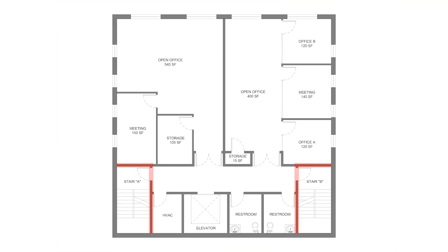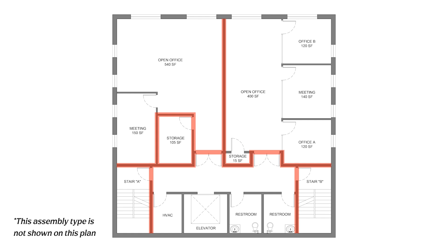Note that stories or numbers of floors in a building include basements but exclude mezzanines. Other walls that must have a one hour fire rating are tenant dividing walls, walls that separate a tenant from a public corridor, storage rooms exceeding 100 square feet, and certain assembly occupancies of 750 square feet or greater with an occupant load of 50 people or more. Some other variables that may determine fire rating are the building occupancy and whether or not the building has an automatic sprinkler system.